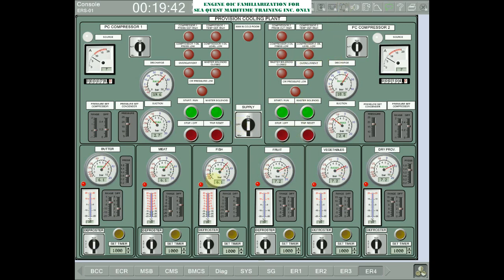Acknowledge the alarm, because there will be alarms on the butter, meat, and fish as they are all above -10 or marker -15. But they also have an alarm on the number 1 and 2 compressors. The pressure outlet is high. So to remove that alarm, increase the pressure setting of the condenser to above 24 bars so that the alarm will disappear. Now it's normal.